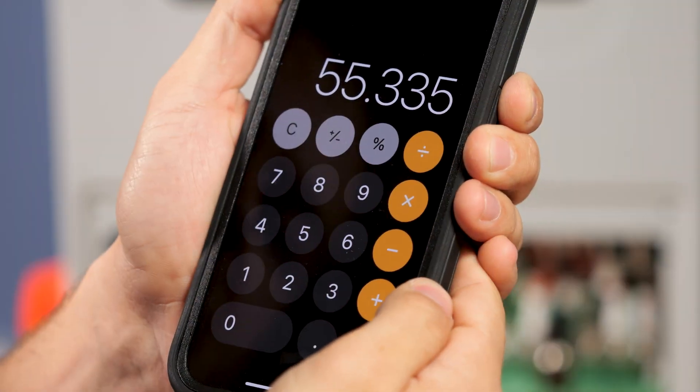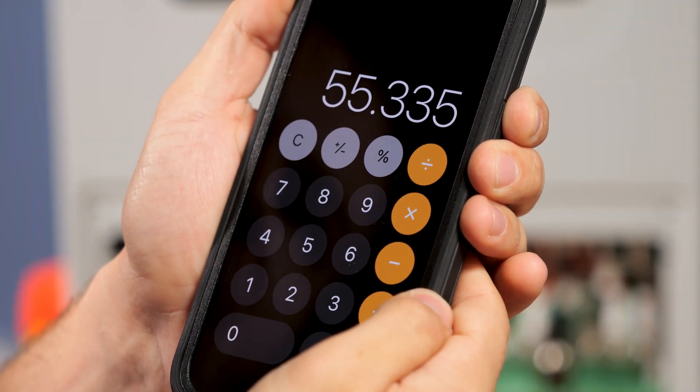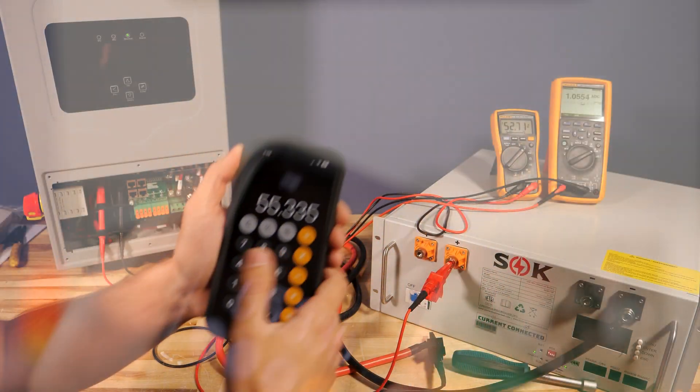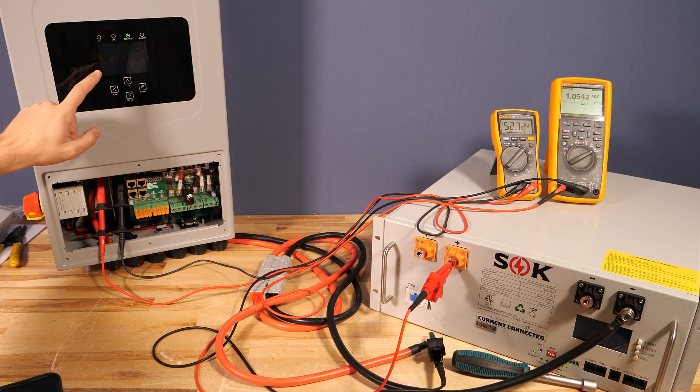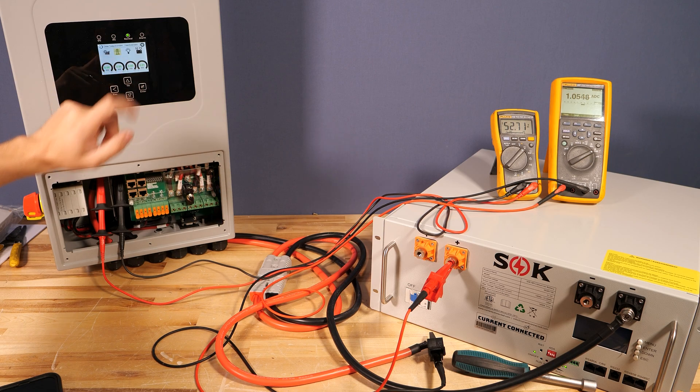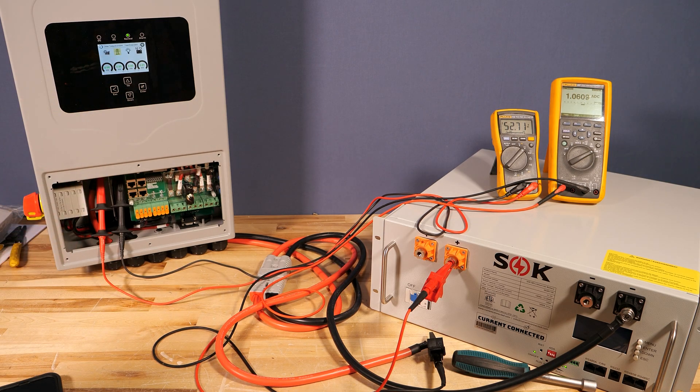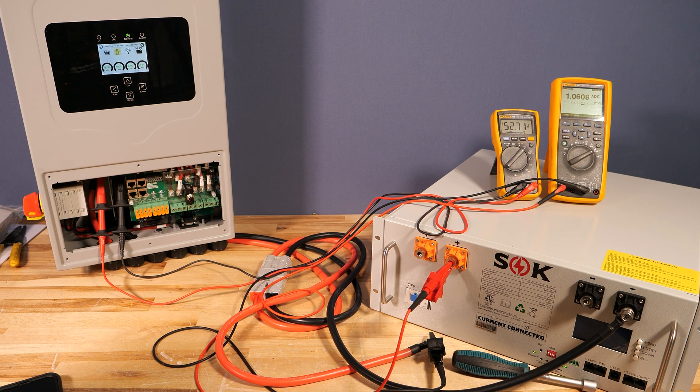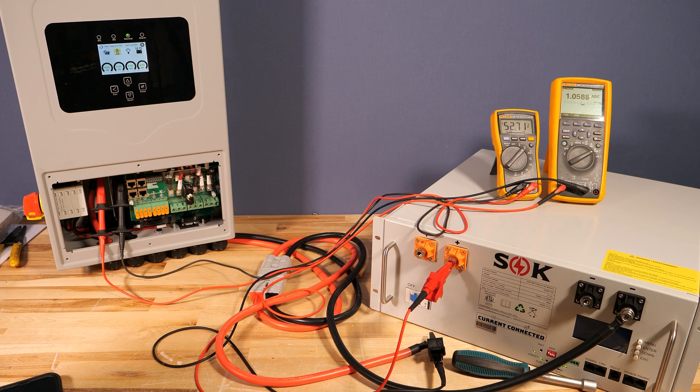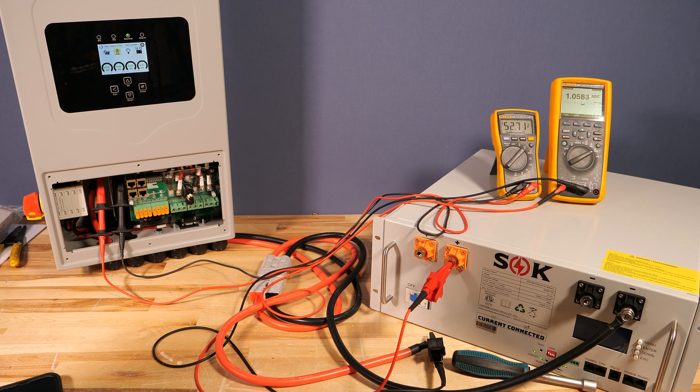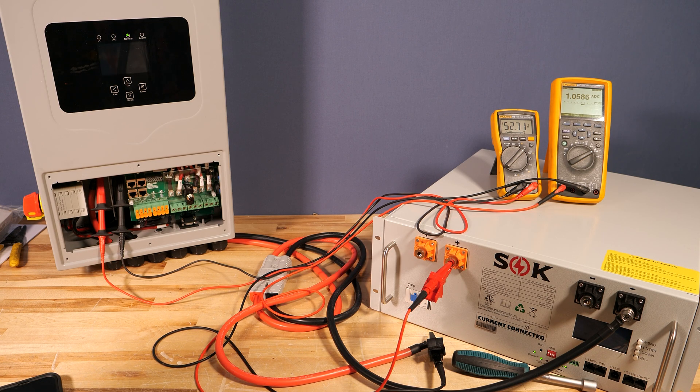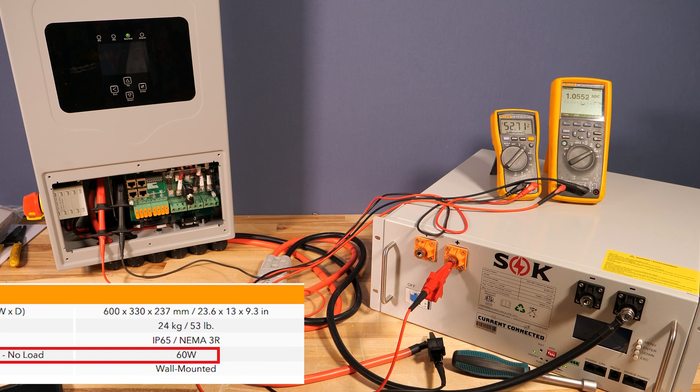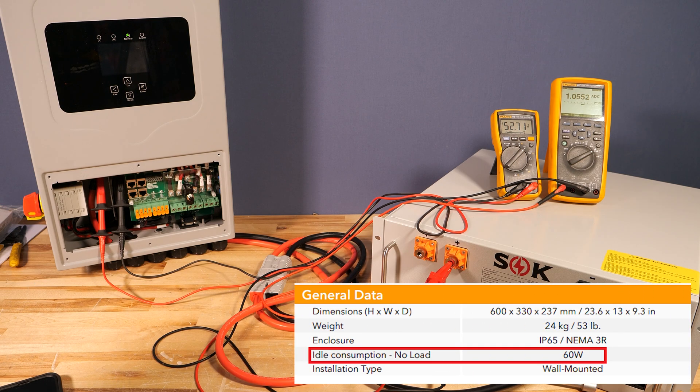You can see right now we're getting 52.7 volts at the inverter terminals and we're drawing 1.05 amps DC. That gives us 55.3 watts of idle draw. One thing to make note of when I touch the screen to turn on the backlight it appears the current only goes up about 5 to 7 milliamps which is a negligible amount. So this is the true idle consumption of the inverter and it is slightly less than the 60 watts noted on the spec sheet.